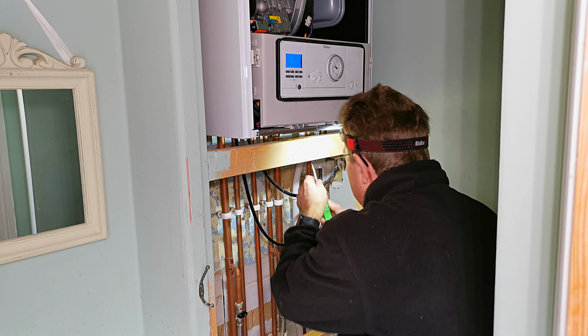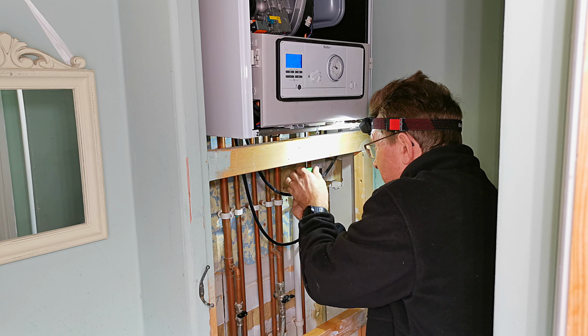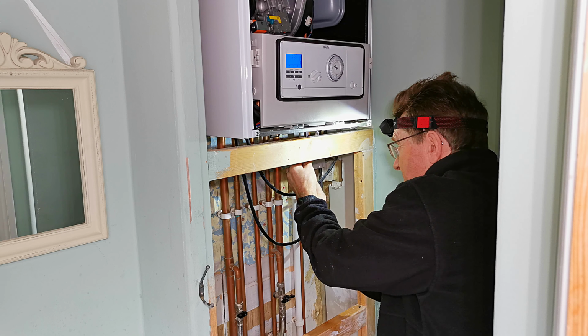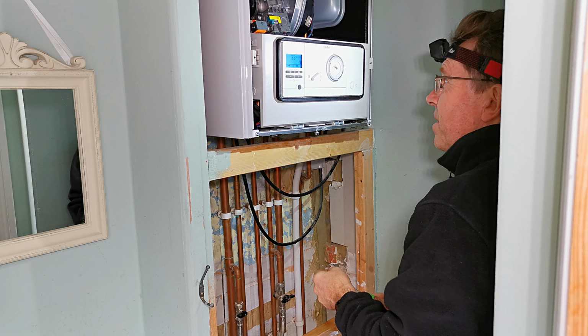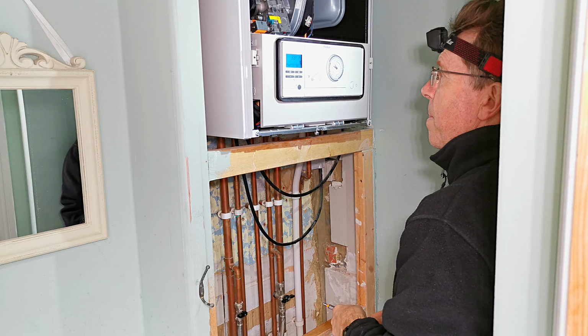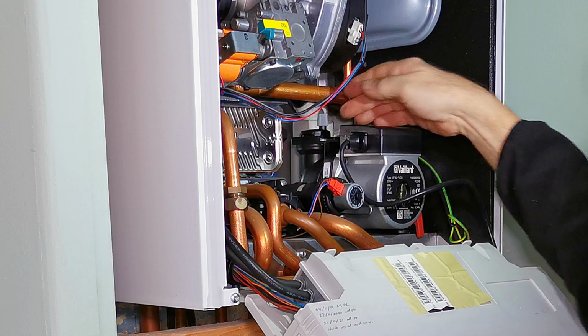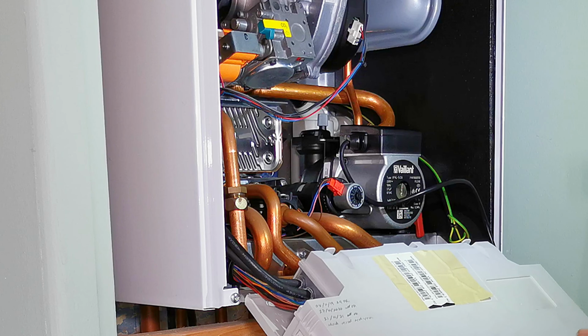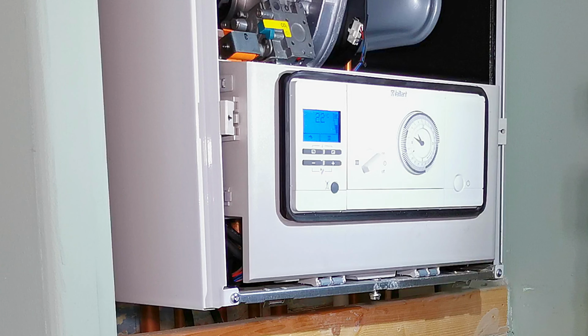I'm now going to open the return valve on the boiler. I'm not going to open the flow valve yet because I want to try and get all the air out of the boiler before it gets circulated around the system. I'm just going to check that the automatic air vent valve is open, which it is. So that's going to let the air out which is in the boiler.